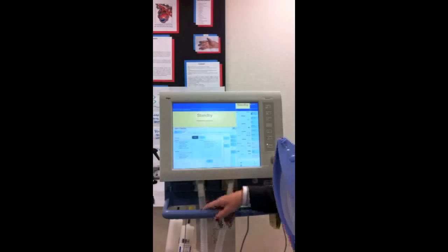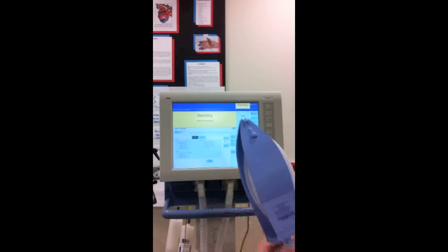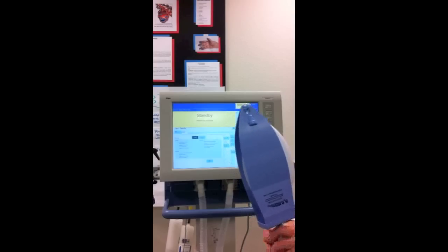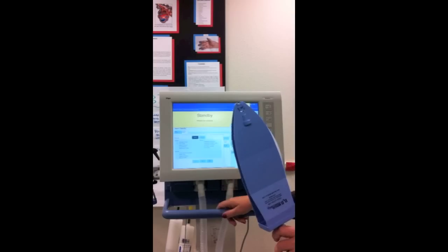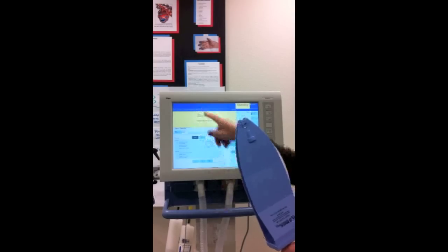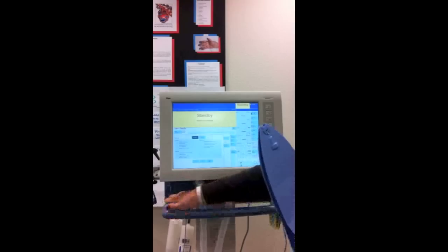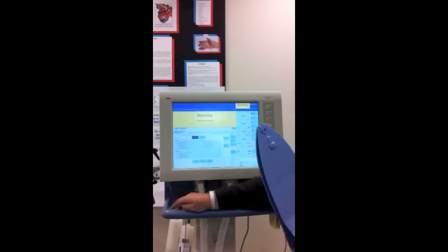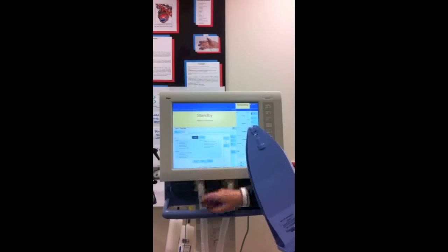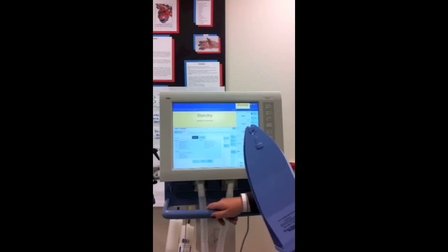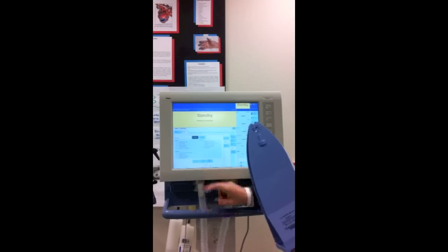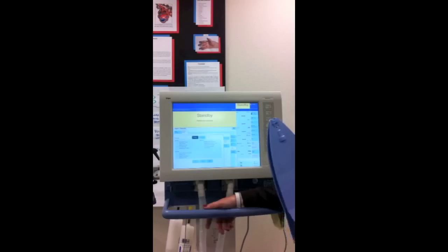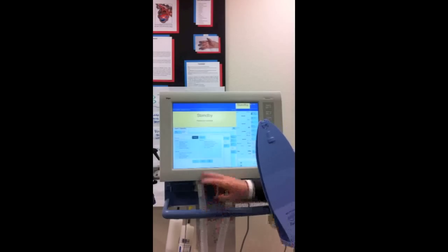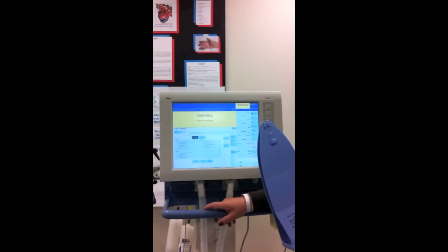And now it says check is active, please wait. Check correct position of the flow sensor. It just wants you to confirm that it's in the right position, in the right way with the door closed. So we've done that, so then we hit yes. Neo sensor placed at the Y piece? No, because we don't have a neonatal. Is humidifier ready for use? If we have a humidifier hooked up, then we need to say yes. Otherwise, we're going to say no because we don't have one right now.